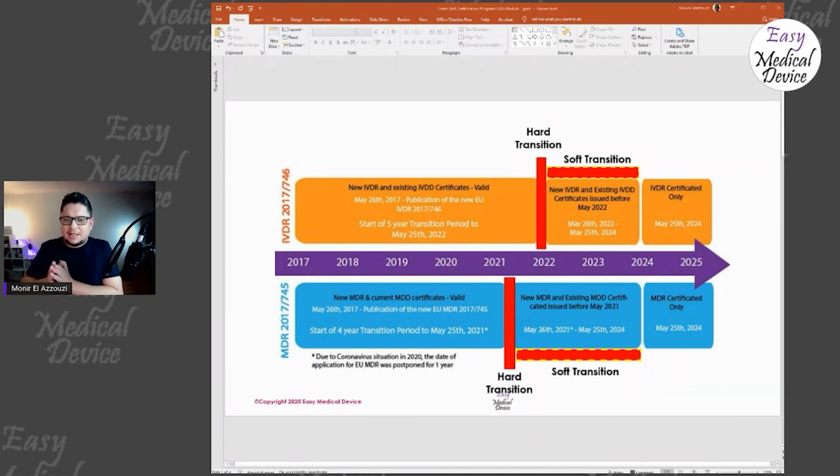I can't remember. We discussed that with Martin Witte of TÜV Süd, 3 to 5 months just to review and to approve that. Then there is maybe some time, like 6 months, to plan an audit if possible. So you have already 9 months here. So just put 3 months more, so 1 year, just in case, because you never know what is happening here.